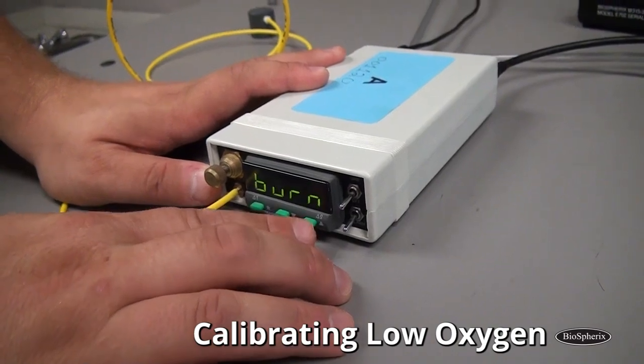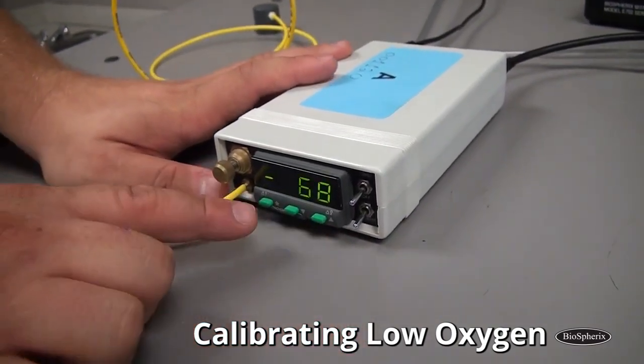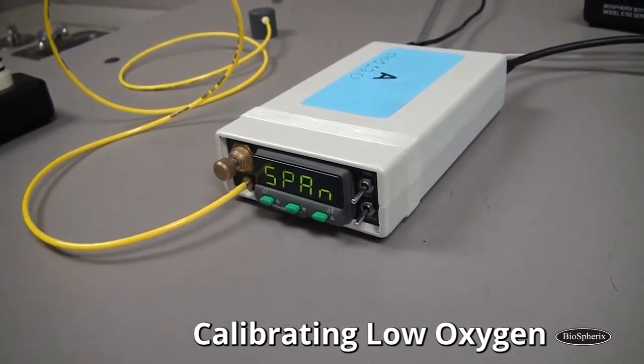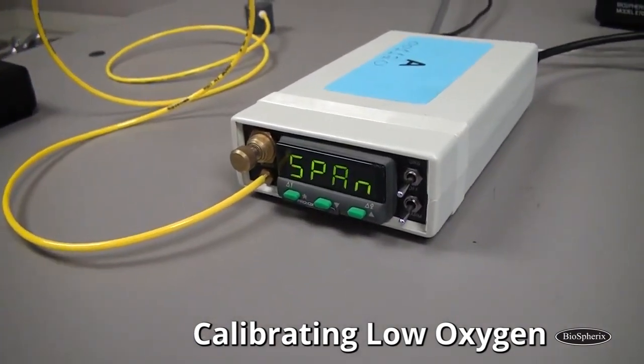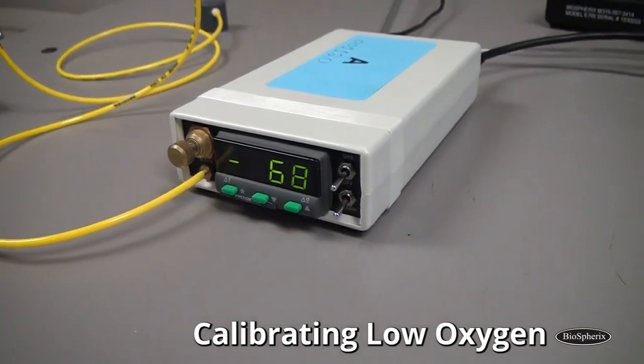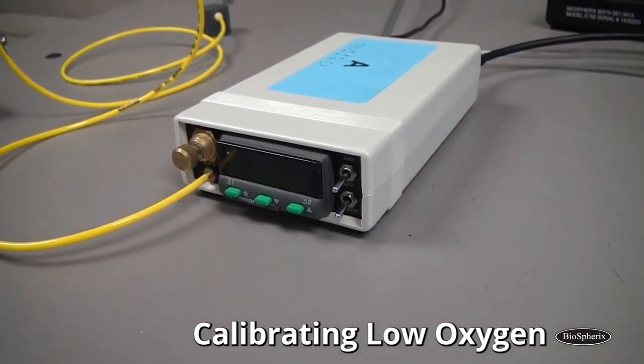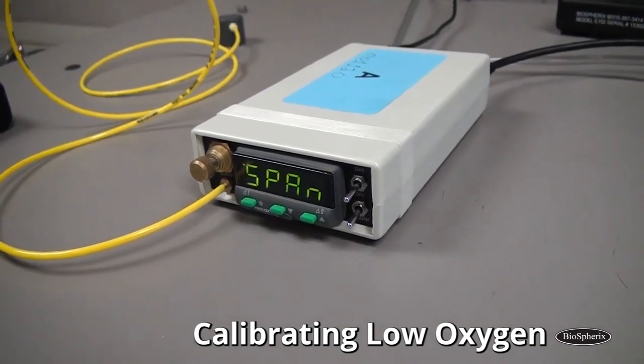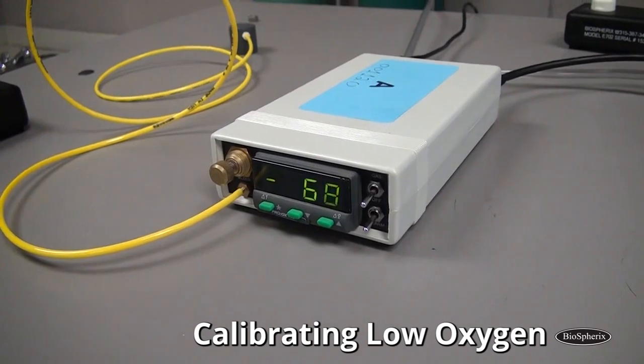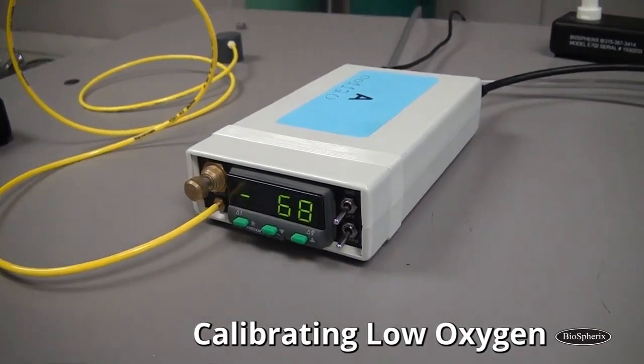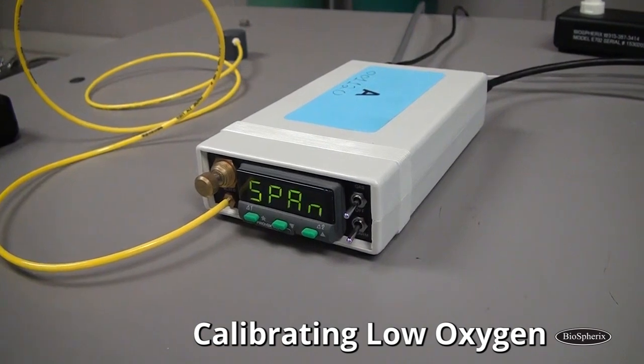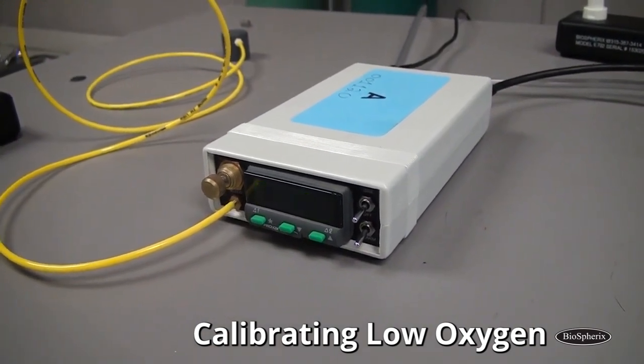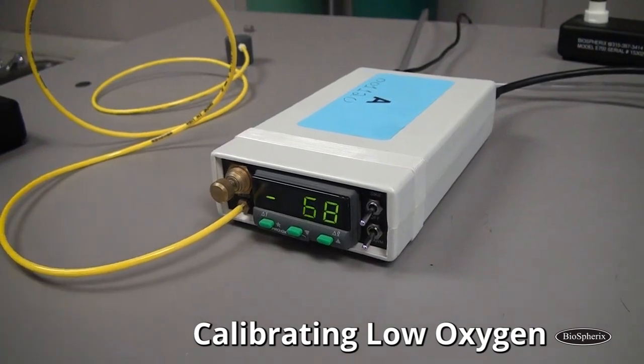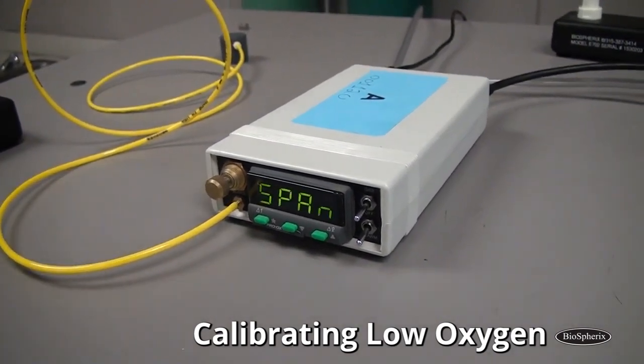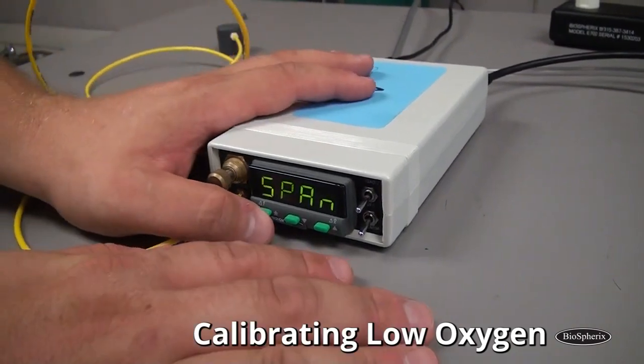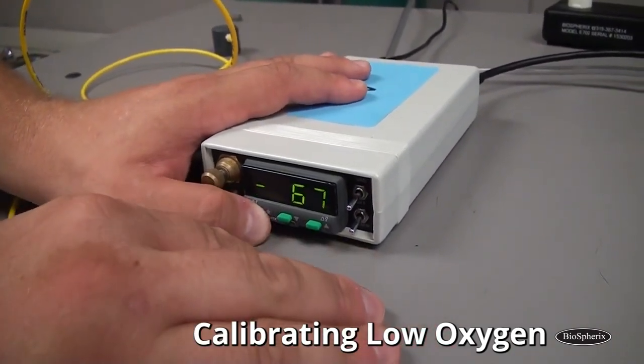So we're going to press up until we see the word span, S-P-A-N, and the N looks weird, but that is supposed to be an N, and that's our coefficient, minus 68. Because it's a coarse adjustment, we know that it's not going to be a 1-to-1, so we just have to make small incremental changes and see how close it gets. We were at 20.3, 20.4, we want to be at 20.8 or close to 21. So I'm actually going to raise this by 1 because we were too low. So you always do the opposite adjustment to the coefficient here. So I'm going to hold the star and raise it up 1.